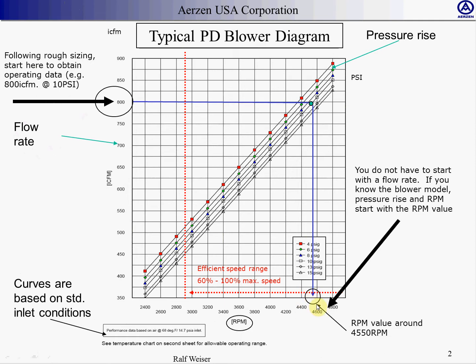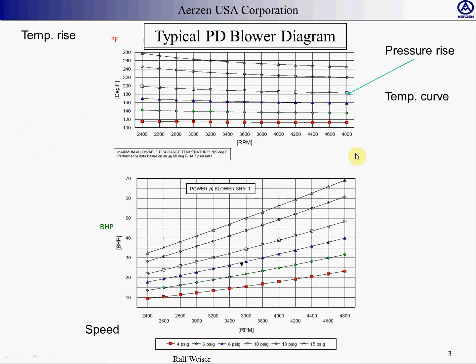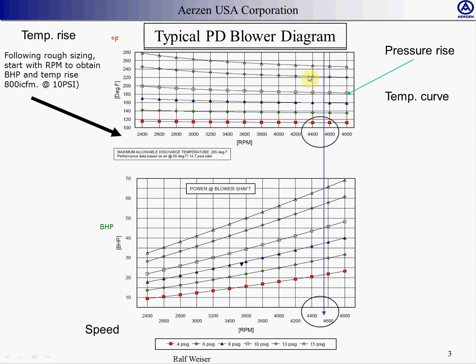Now that you know what your RPM is, you can go to the part of the diagram that will list what my temperature rise is and my expected brake horsepower at the drive shaft. Following what I get from the other sheet, I draw the same vertical line through my 4,550 RPM and here I draw a horizontal line over at the temperature curve, which you can see down here is 10 psi. So my horizontal line is about 180 degrees. My temperature rise plus my ambient is approximately the air discharge temperature. This is very important and this is where my ambient temperature makes a huge difference. So at 68°F I might have this, but if I have 100 degrees ambient, it's 32 degrees hotter than that.